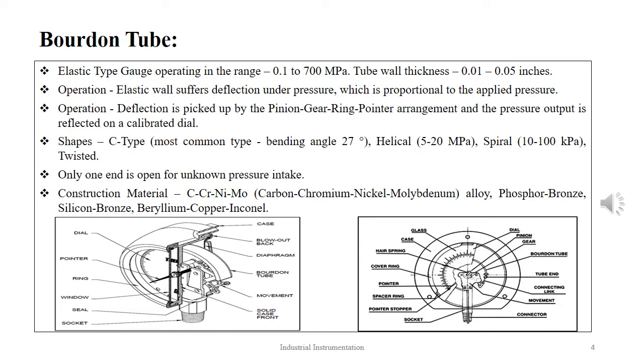The unknown pressure is connected to the free end and this pressure acts on the inner wall of the Bourdon tube. As the fluid pressure enters the Bourdon tube, it tries to be reformed, and because of a free tip available, this action causes the tip to travel in free space and the tube unwinds. The applied pressure tends to straighten up the tube, which is either circular or spiral or helical in shape. The tube undergoes deflection which is proportional to the applied pressure. This deflection is read out by the gear, pinion, ring pointer arrangement. The pointer assumes a new position with movement in the pinion section.